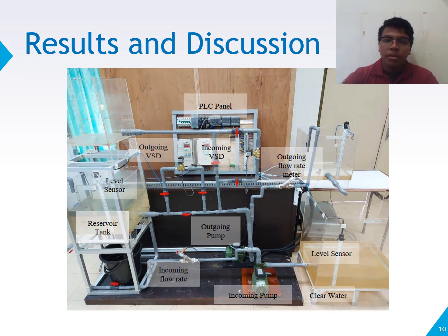This is our lab bench system that has been scaled down compared to a real plant. The PLC receives analog input from the liquid level sensor here, from the reservoir and clear water tank. Then the signal is sent to the variable speed drive, VSD, to regulate and control the speed of the motor pump incoming and outgoing, thus controlling the water level and manipulating the flow in the tank.